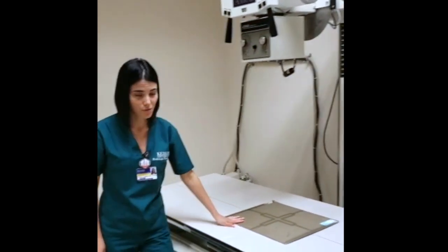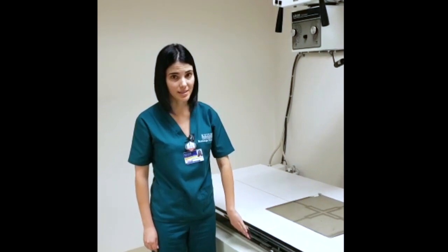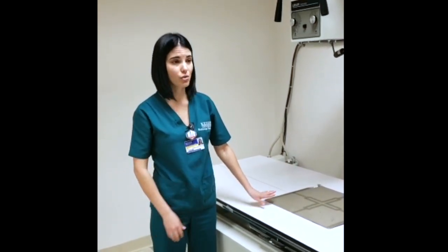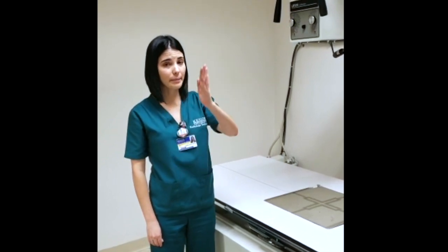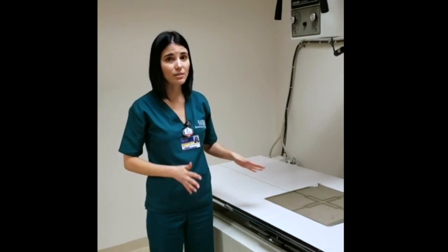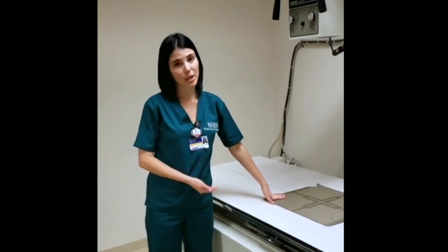So the error comes from having 2 grids. Aligning the lead strips of each grid is really hard. We have parallel lines in the middle and then a little bit slanted from the sides. Aligning those sides for both grids is really difficult. That's why we get the double grid error. Even though we need a double grid because the patient is really thick, we will get that error in the image.